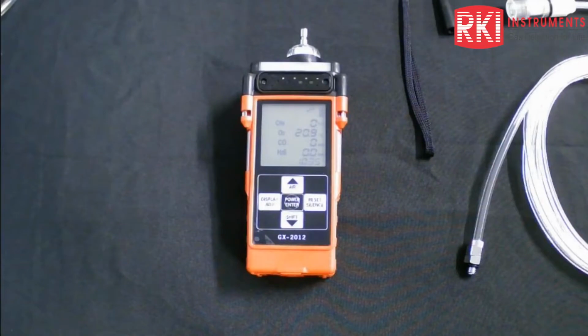Bob and I were doing some calibrations the other day, and we took a look at what happens when you put on a regulator that is a 1 liter regulator or even more, and it causes the sensors not to read correctly, which in turn will not calibrate the instrument correctly. So when you are looking at calibration, make sure that you supply your guys with the correct tools. Bob, I'm always going to suggest that you use a demand flow regulator, so we allow the function of the pump to do that for the calibration process. It's just a good note to point out, because many people will not do that and will use a fixed flow regulator on a unit that has a pump. It just leads to problems, and we want to avoid that. Good point, John.